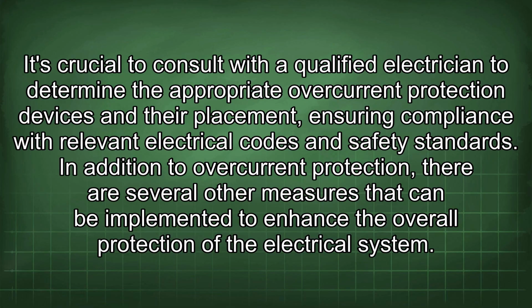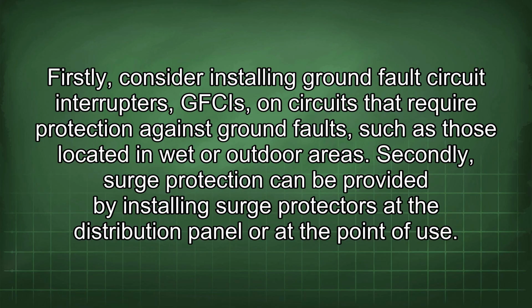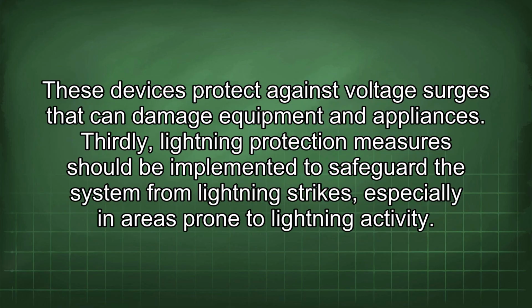In addition to overcurrent protection, there are several other measures that can be implemented to enhance the overall protection of the electrical system. Firstly, consider installing ground fault circuit interrupters, GFCIs, on circuits that require protection against ground faults, such as those located in wet or outdoor areas. Secondly, surge protection can be provided by installing surge protectors at the distribution panel or at the point of use. These devices protect against voltage surges that can damage equipment and appliances.